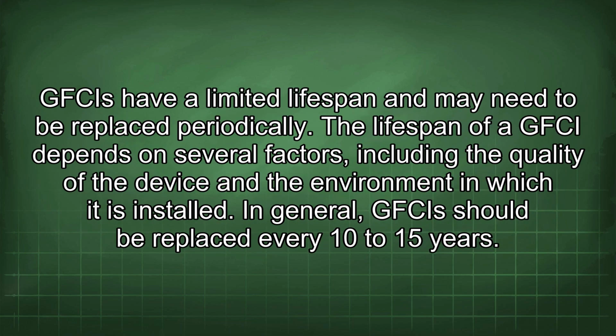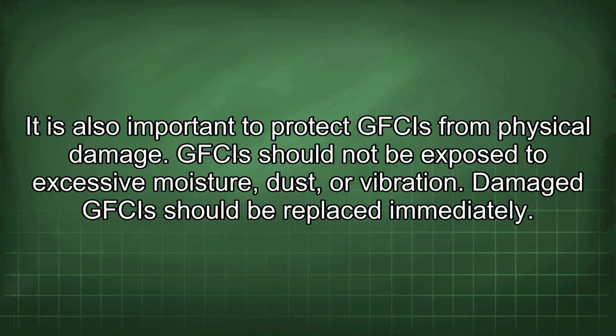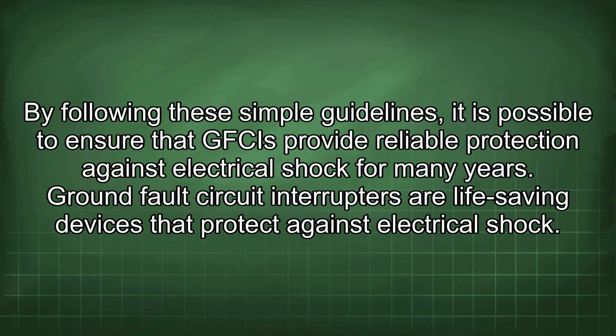GFCIs have a limited lifespan and may need to be replaced periodically. The lifespan of a GFCI depends on several factors, including the quality of the device and the environment in which it is installed. In general, GFCIs should be replaced every 10 to 15 years. It is also important to protect GFCIs from physical damage. GFCIs should not be exposed to excessive moisture, dust, or vibration. Damaged GFCIs should be replaced immediately. By following these simple guidelines, it is possible to ensure that GFCIs provide reliable protection against electrical shock for many years.